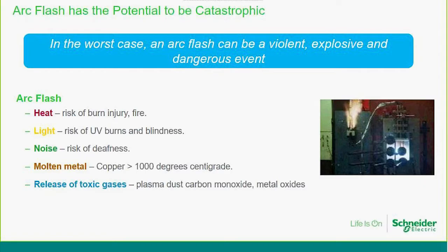And that's why a lot of the switchgear construction tries to prevent you from seeing any of that. You've seen, particularly for medium voltage switchgear, huge strides forward in the construction of the equipment to try and dissipate any internal arcing in a safe manner. That's IEC 62271. We're beginning to see equivalents in the 61439 switchboard standards, which talks about particular arc venting chimneys to try and prevent any operators from actually experiencing this. But that's in a new world. The challenge we've got is a lot of our electrical infrastructure is old and doesn't have these features built in. So we have to take that into consideration.